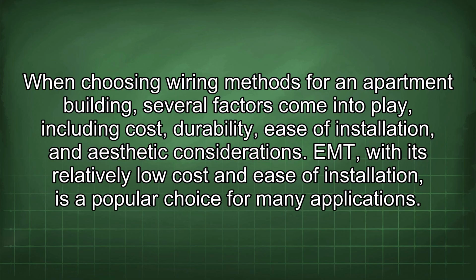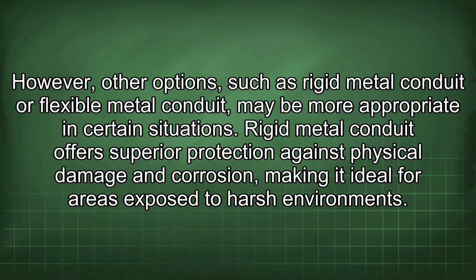When choosing wiring methods for an apartment building, several factors come into play, including cost, durability, ease of installation, and aesthetic considerations. EMT, with its relatively low cost and ease of installation, is a popular choice for many applications. However, other options, such as rigid metal conduit or flexible metal conduit, may be more appropriate in certain situations. Rigid metal conduit offers superior protection against physical damage and corrosion, making it ideal for areas exposed to harsh environments.